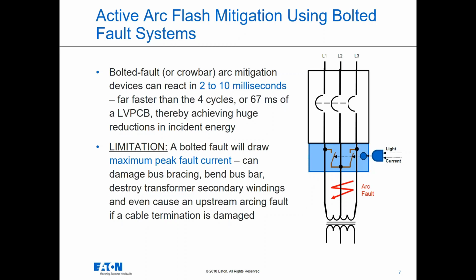By doing so, they react fast enough to change the mathematical equations in favor of a reduction in incident energy by basically fault closing on the line. So that way the arc fault incident energy doesn't flow downstream to the point of the arcing. It actually creates a bolted fault current through the upstream portion of the system. But that comes with consequences and limitations as well. If we do a bolted fault above the arc fault, the maximum peak fault current would be drawn either through the secondary of a transformer or provided downstream from all the upstream sources.